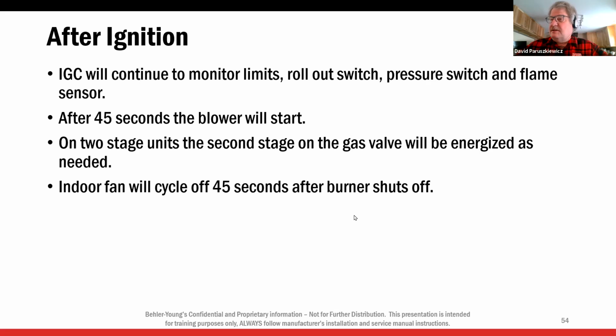So we just talked about the sequence of operation of the IGC, integrated gas control. Once ignition is started, we're going to continue to monitor limits. After 45 seconds, the blower will start. Now, again, we can't change that, but it'll adjust itself. We'll talk about that in a minute. On a two-stage unit, the second stage will ignite according to the thermostat. Indoor fan will cycle off 45 seconds after the burner shuts off. Again, that will adjust itself. We can't adjust that.